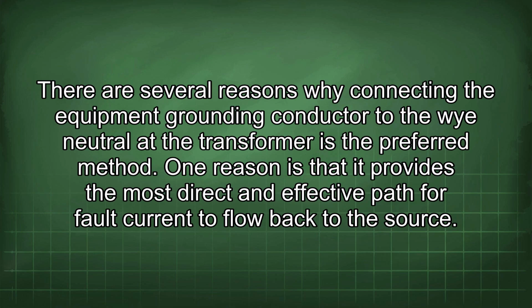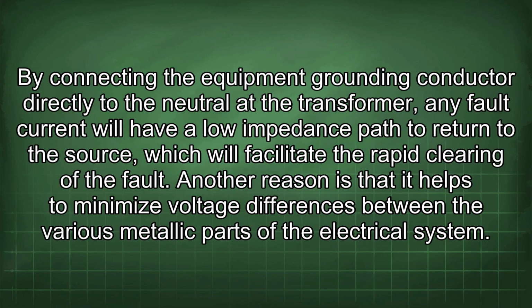There are several reasons why connecting the equipment grounding conductor to the Y neutral at the transformer is the preferred method. One reason is that it provides the most direct and effective path for fault current to flow back to the source. By connecting the equipment grounding conductor directly to the neutral at the transformer, any fault current will have a low impedance path to return to the source, which will facilitate the rapid clearing of the fault.